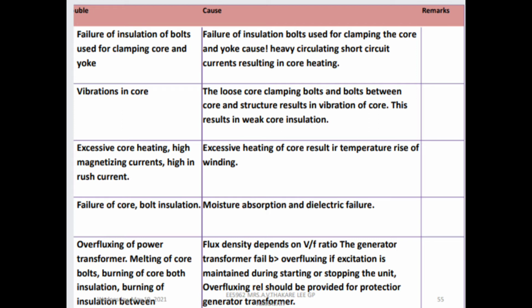Trouble is vibration in core. Cause is the loose core clamping bolts and bolts between core and structure result in vibration of core. This results in weak core insulation. Excessive core heating: high magnetizing current and high inrush current cause excessive heating of core, resulting in temperature rise of winding. Trouble is failure of core bolt insulation, which causes moisture absorption and dielectric failure. Failure is overfluxing of power transformer, melting of core bolts, burning of core bolt insulation, burning of insulation between.